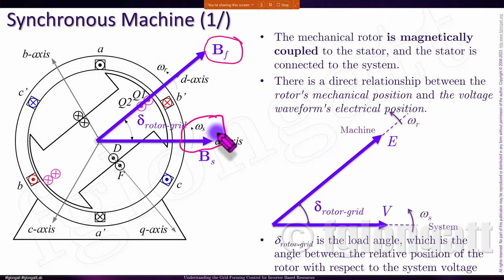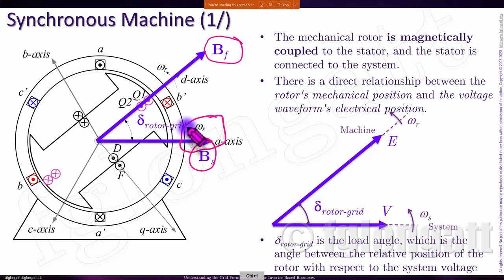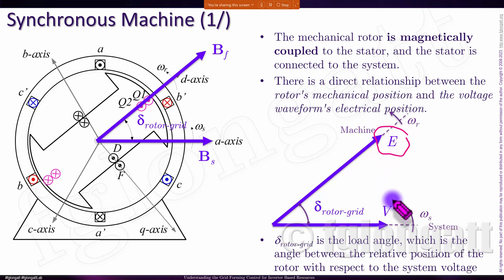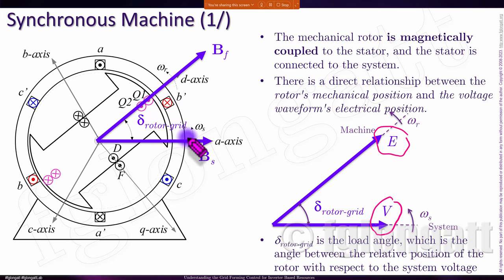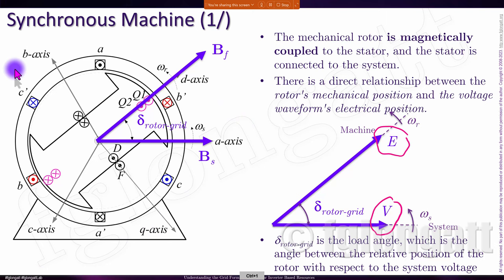I will assume the electrical power system is extremely strong — we can assume it is an infinite bus bar. So the magnetic field related to the stator will be rotating at constant speed, numerically equal to the synchronous speed. This magnetic field can be transferred into voltages — the internal voltage of the synchronous machine. We can say this is the voltage coming from the network, and the angle between these voltages is identical to the angle between those magnetic fields. We call that delta, or basically the load angle, representing the relative position between the voltages or the magnetic field.